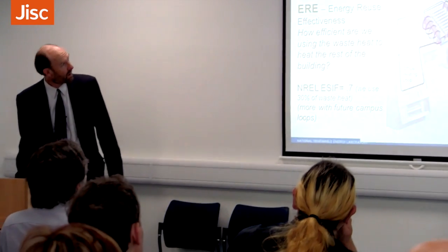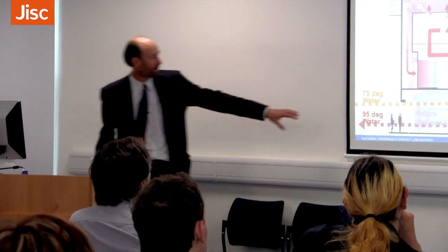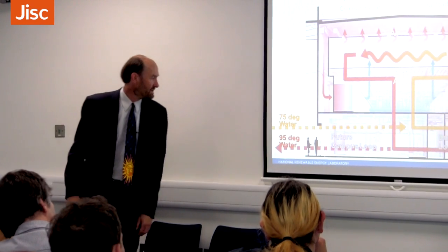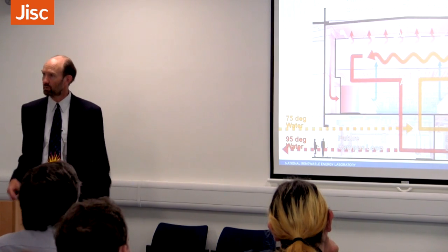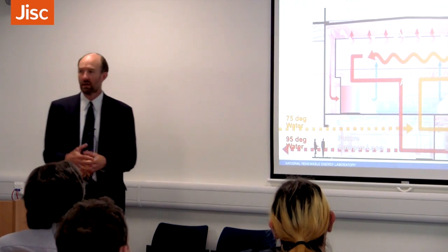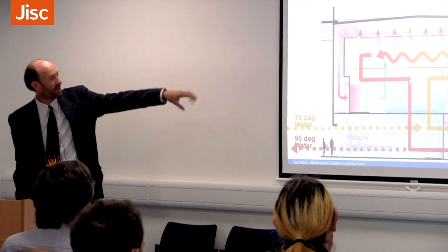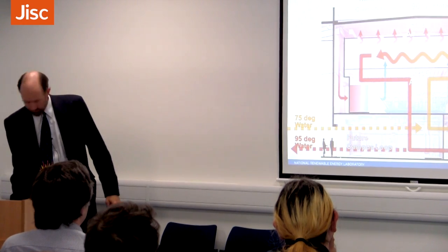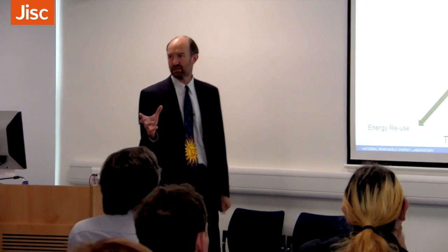Here's the cross-section showing 75°F (24°C) water going in and returning at at least 95°F (35°C). We ended up buying HP equipment — Cray and others are very similar. About 10% goes to air, 90% goes direct liquid to the racks. Some takeaway messages: think three-dimensional optimization. We know how to build energy-efficient data centers — if you're not getting in the 1.1 range, you can do better. We also need to look at IT consumption — watts per flop — and energy reuse.